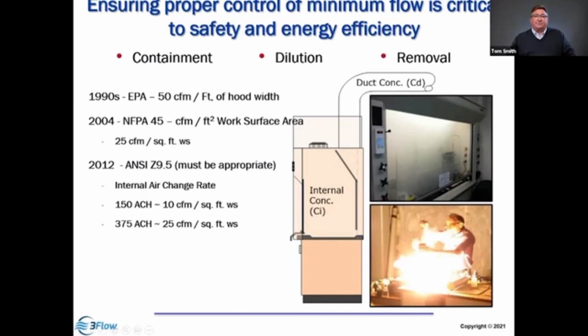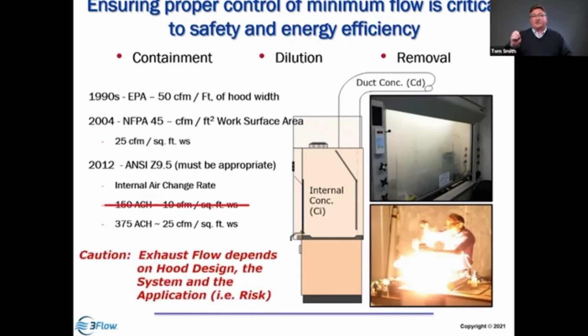The Z9.5 standard said it should be based on air changes per hour. The width times the depth times the height. That is your internal volume. And now you can calculate an air change rate that is appropriate to dilute and remove the materials. So the recommendation was somewhere between 150 and 375. I'm going to express caution. A lot of people are operating hoods at a flow that is too low. 150 air changes per hour may be good for energy consumption, but it's potentially problematic from a safety standpoint and could put the hood into a situation where you get loss of containment or escape, we get poor dilution, and the inability to essentially remove the materials from the hood and the duct system. So that minimum flow is critical.